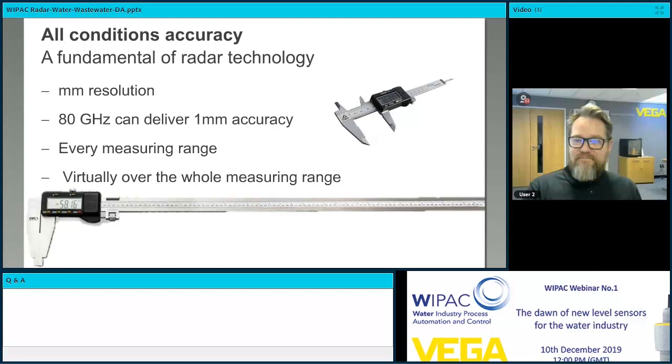Those numbers are regardless of the overall measurement range. Radio waves don't stretch out like a sound wave in measurement range. As the range gets longer and the frequency gets lower, you tend to find that the actual wavelengths get longer, and so you lose a bit of accuracy. And of course, over those longer ranges, it's even more difficult to measure temperature evenly over that range.